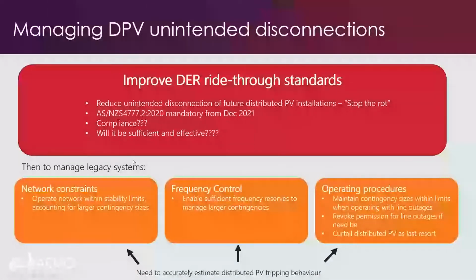However, this only applies to new inverters, so we still have almost 2 gigawatts in South Australia and a very large amount across the NEM of legacy systems installed under the old standard, which we still need to manage. We're doing that with a combination of network constraints, so that we're operating the network within stable limits, accounting for the larger contingency sizes that we now have in high PV periods, making sure that we enable sufficient frequency control reserves so that we can manage those larger contingencies, and updating our operating procedures so that we take additional action when required. Particularly this occurs around periods where we've got major line outages happening, in which case we can't handle as large contingency sizes.